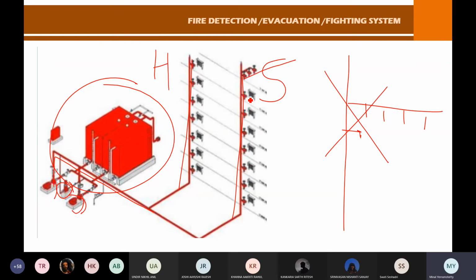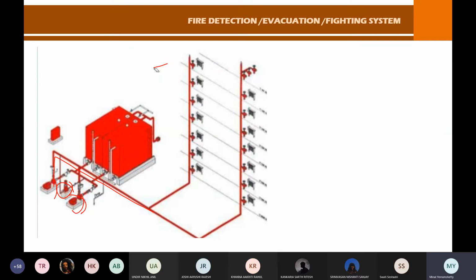I doubt you'll get that kind of detail in your case study, but just in case you need it, these are some common things, because in fire safety one has to be clear about one thing: in the pipe, the pressure should be maintained. If that pressure drops, the pipes are useless. So there has to be a separate wet riser - you'll need a separate sprinkler, separate booster for both the fire riser and everything else.